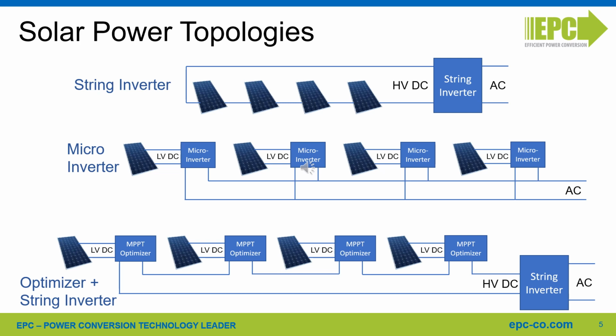An alternative topology that is getting a lot of traction with big sponsors like SolarEdge and Tigo consists of several optimizers, one per panel or one every 2 panels, plus a single inverter. A power optimizer is a DC to DC converter that maximizes the energy harvest from a solar panel through MPPT. Single or dual panel solutions are available in the market up to 800 watt.